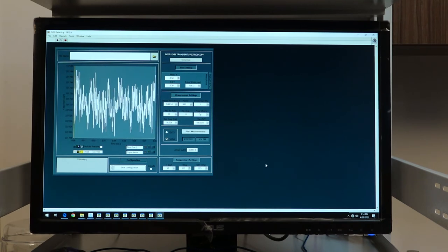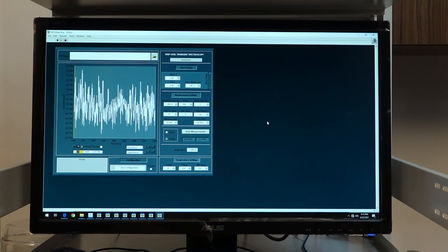You see that this number popped up on the right hand side; if I click it again, this number is showing the noise level in the capacitance transient. It is of the order of a few femtofarads, whereas our signals are in picofarads, so that would not hamper our actual measurement much. Our goal is to minimize this noise value by optimizing these parameters before starting a DLTS scan.